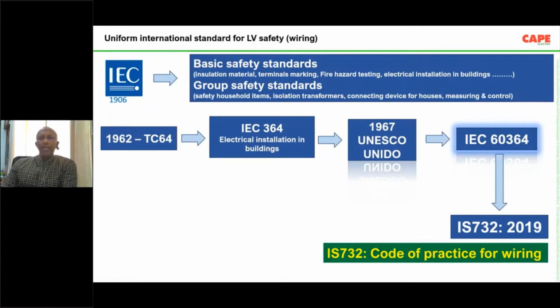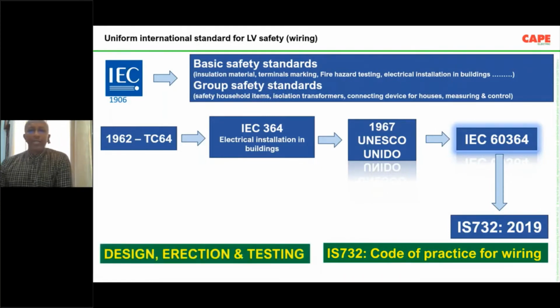As I said, in other countries, for example in the UK, the equivalent is called BS 7671. Any building in the UK that does not conform to BS 7671, you can be sure they will not get electricity. So conformation to the standard is highly important in those countries. In India, this is called IS 732, and this is the standard which talks about design, erection, and testing. What parameters should you look at while designing, erecting, and testing a building?